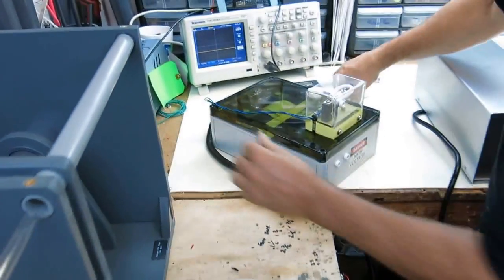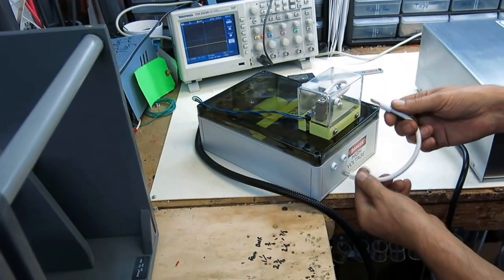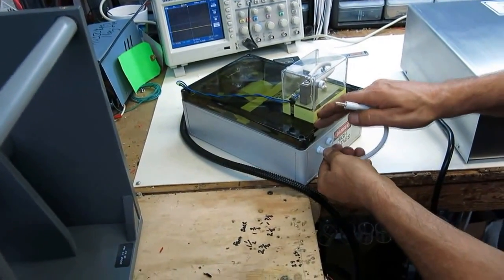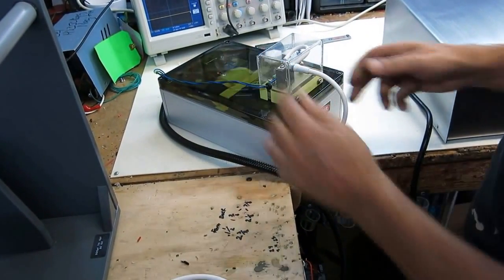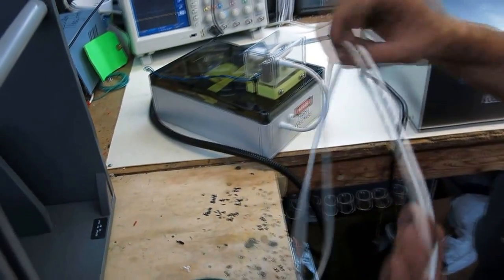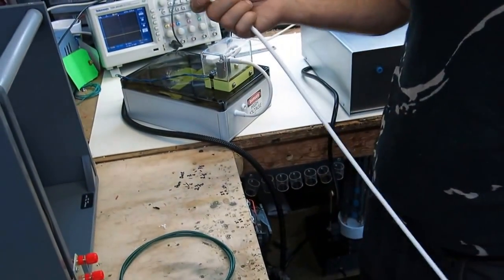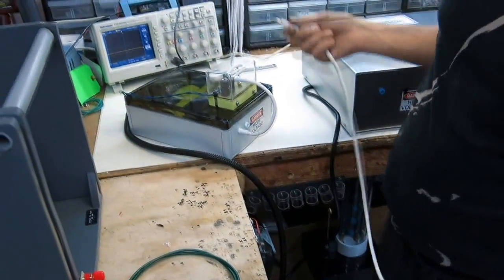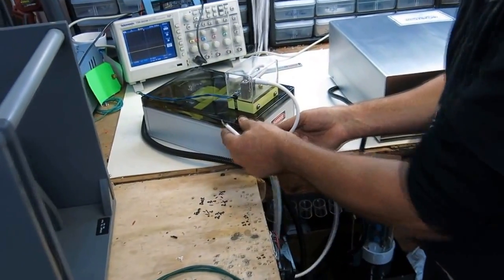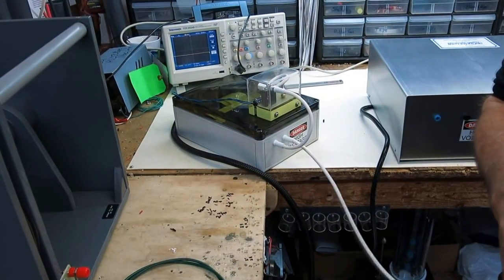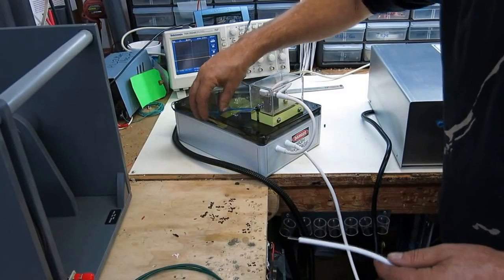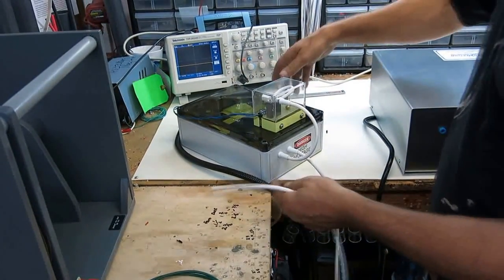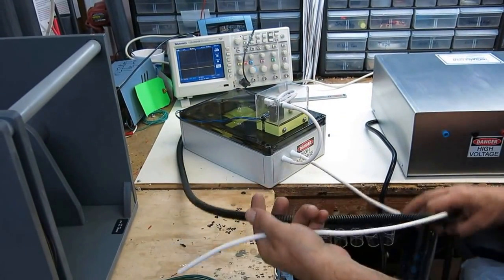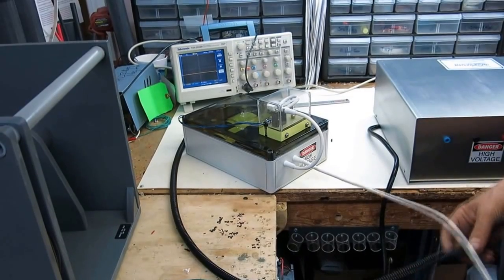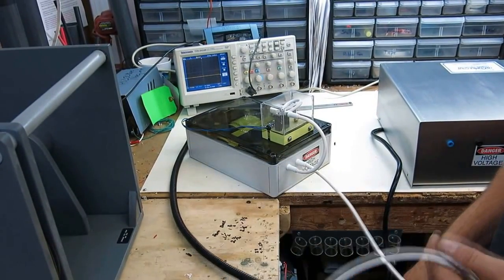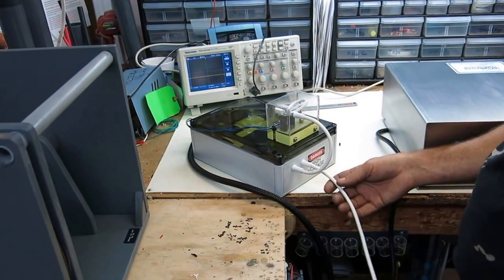So then you have this little short high voltage wire here, which can go either one of these - I put it there and there. Your high voltage out to your capacitive load, it's going to be a capacitive load. The whole idea of the remote oil transformer is that in low capacitance loads, you want to get it as close to the load as possible. So that wire can be shortened if necessary.